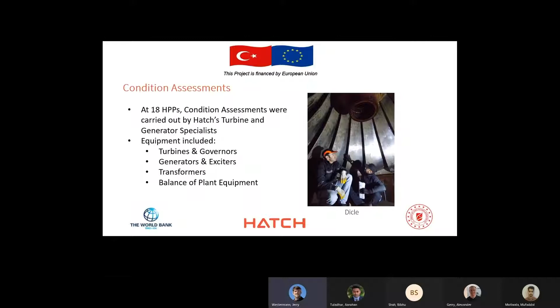The efficiency monitoring systems, which were quite innovative, I can certainly say. At 5 of the 22 plants, a somewhat traditional acoustic flow measurement system was installed. These are permanent acoustic flow measurement systems installed inside the penstocks just upstream of the inlet valves. And at the other 17 plants, a differential pressure system, as we call it, which essentially takes readings off of the Winter Kennedy taps of the spiral case.